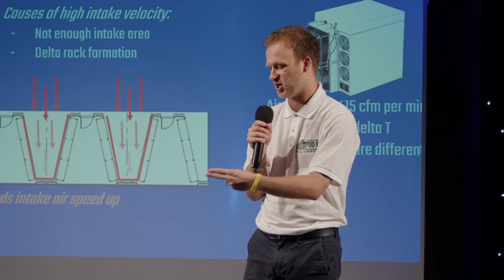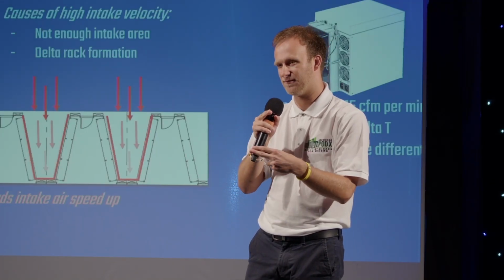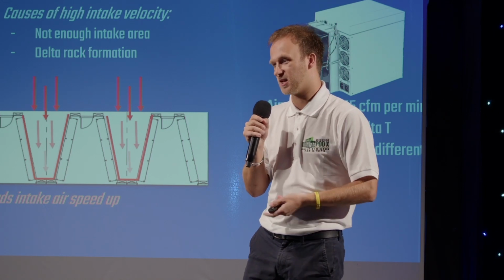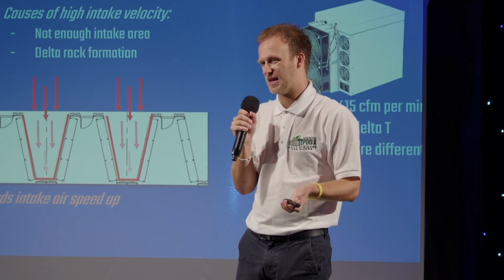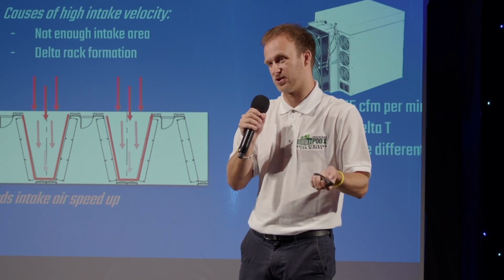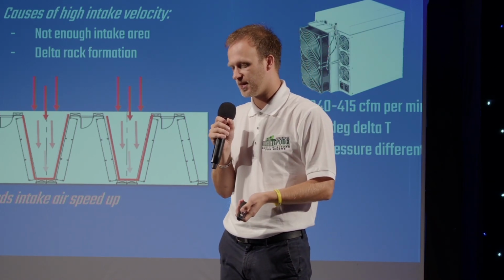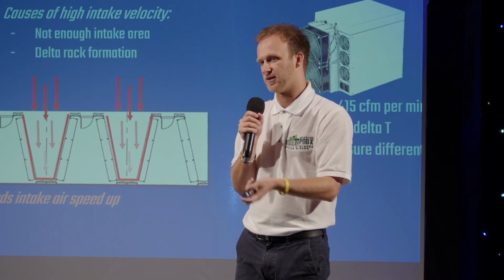They're not able to suck in and overcome that high velocity to get the air they need. They actually starve. So you might get overheating in those front columns at lower temperatures than you might think. And it's just the way the delta is. Again, they're really good for density, but you get this high intake problem. And again, because of your high intake, you can get that hot air recirculation from the outside. So everything is kind of connected.